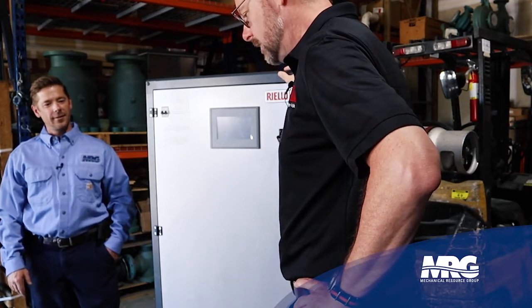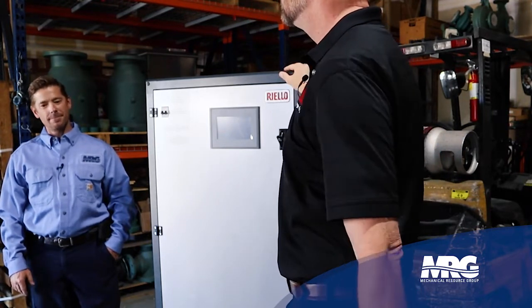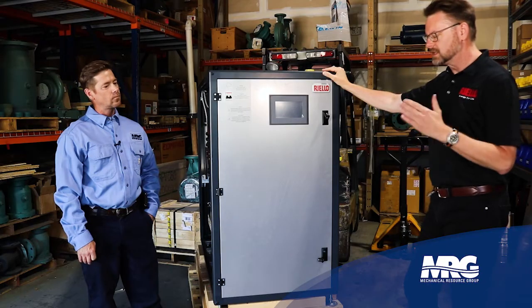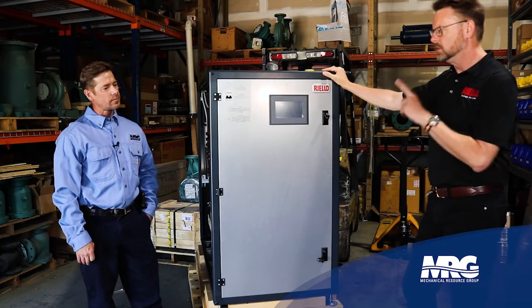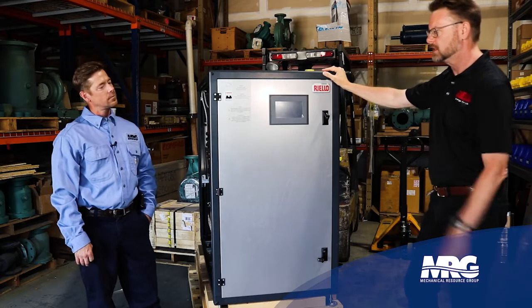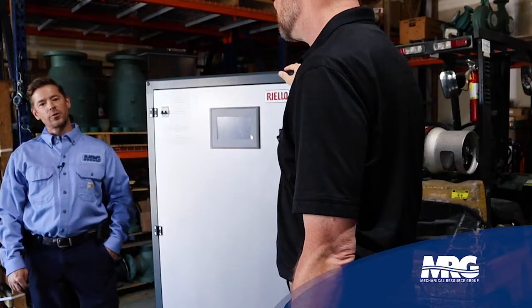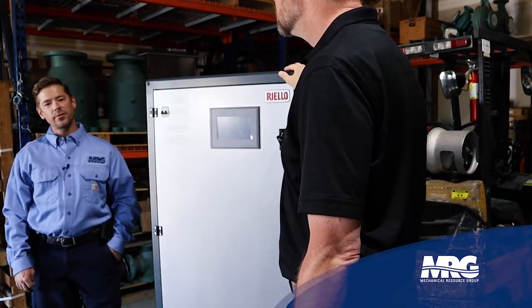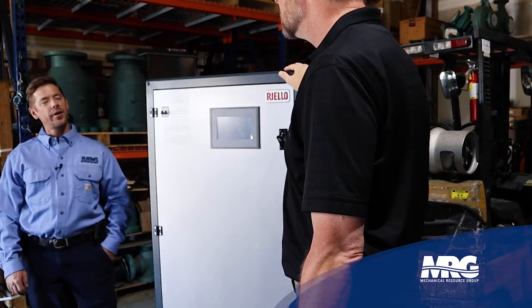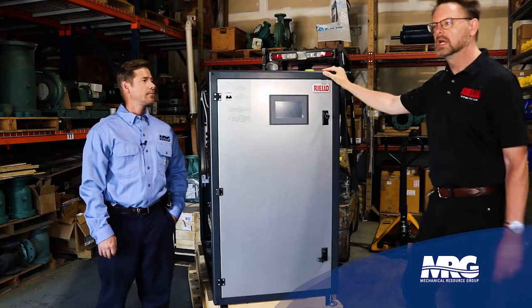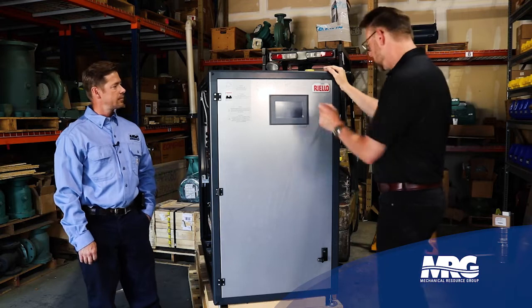You've been out on some calls where you've had some boiler failures. That's right. If you could, what are some of the recent problems you've run into, one at a time? What was a problem that you got called to resolve on a boiler? The most recent one, probably the most common one, is failure to ignite. An ignition failure. Okay, good.